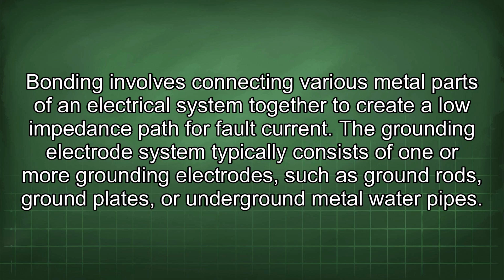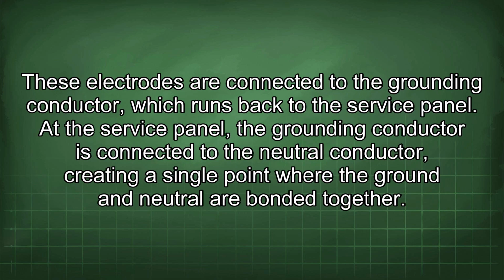Bonding involves connecting various metal parts of an electrical system together to create a low impedance path for fault current. The grounding electrode system typically consists of 1 or more grounding electrodes, such as ground rods, ground plates, or underground metal water pipes. These electrodes are connected to the grounding conductor, which runs back to the service panel. At the service panel, the grounding conductor is connected to the neutral conductor, creating a single point where the ground and neutral are bonded together.